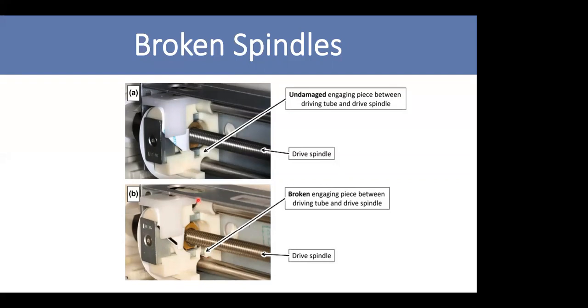So when this happens, if the drive spindle is broken, you're going to see fluid movement that is uncontrolled, or it's not going to move at all. It depends on the condition of the break, what type of break happened. In some cases, the spindle still moves, but it moves freely. That's dangerous actually.